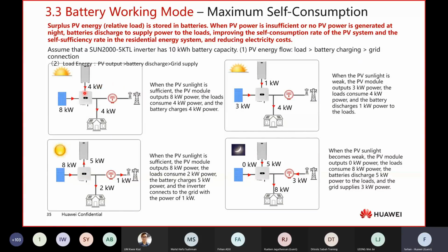Okay, for the first scenario, let's say your PV system is enough to generate a maximum of 8 kilowatts. During that time, only 4 kilowatts of load is on that side. So the remaining will be charging the Luna 2000. Sorry, the arrow should be up, lah. Okay, for example, during the very high peak, your load is less, 2 kilowatt, and then the remaining will start to charge the battery Luna at 5 kilowatt, and the remaining will be sent to the grid.